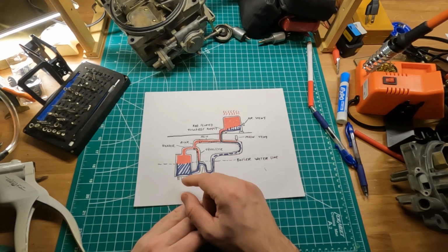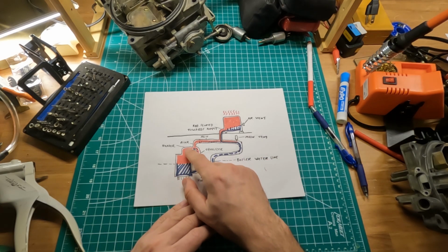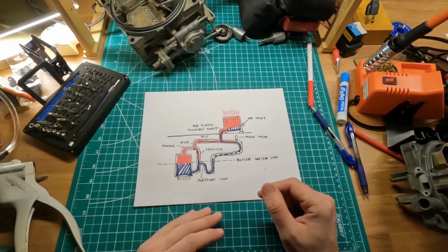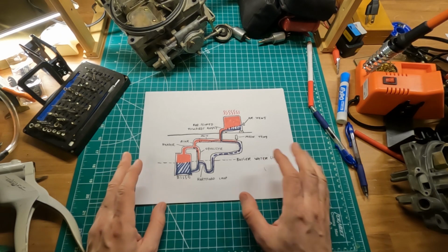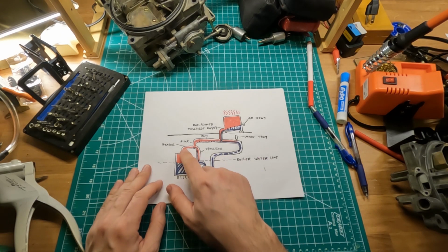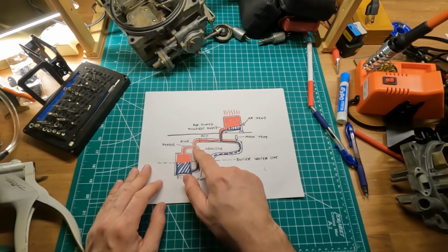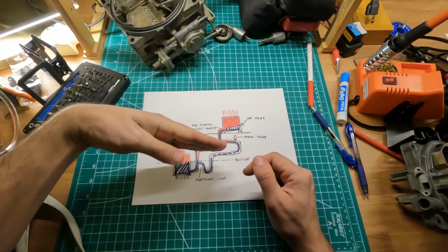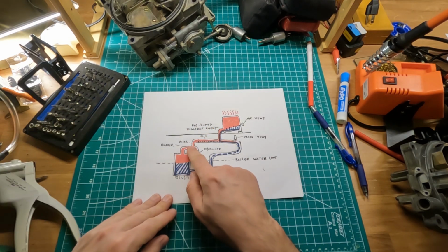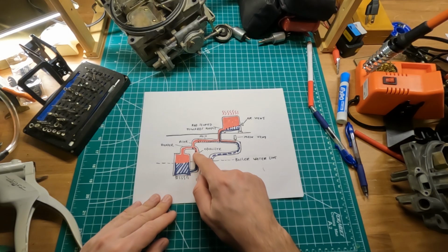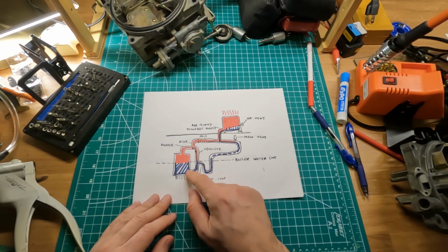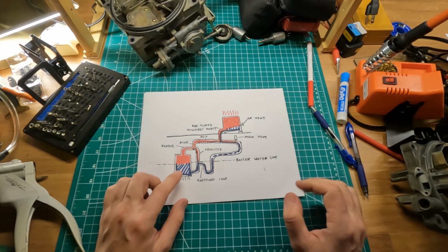When steam loses velocity, it also loses some of its wetness. Of course, we're using the totally wrong terms. That wetness, or condensate, returns back via the header that's pitched in this direction. So the water goes down, and then this condensate returns back via the equalizer into the boiler.